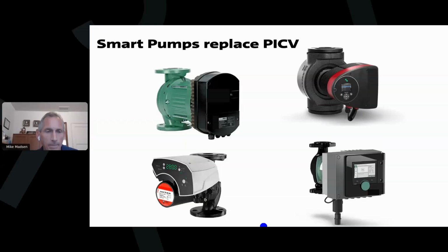I'm going to ask you one, and there are a few comments in here, so I'll ask them too. My question is, suppose you're an energy engineer and they have a primary-secondary system. The secondary system is, for some reason, constant volume pumping. You're going to recommend putting a variable frequency drive on that chilled water pump, and maybe it's just a standard motor, and maybe we should replace the motor as well so it doesn't burn out. So question number one is, do you recommend that we replace the motors? Because I've heard different people say different things. One, you need inverter duty motors, and some people say no, you can just run the standard as long as the distance between the drive and the motor is not too long, etc.